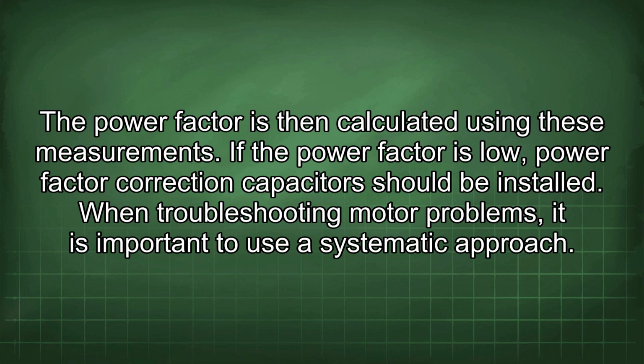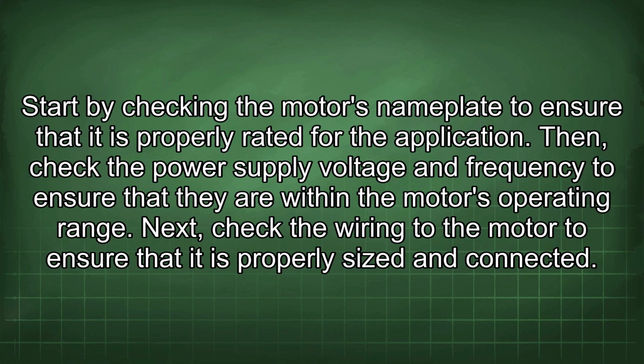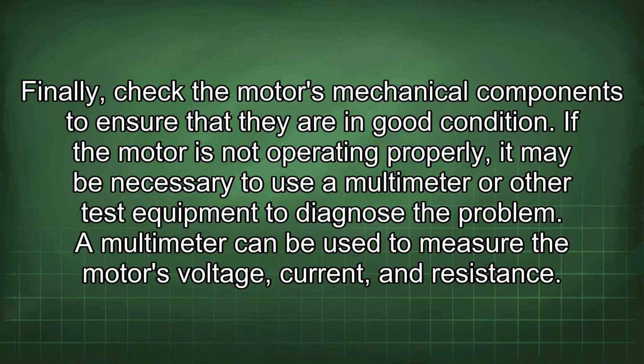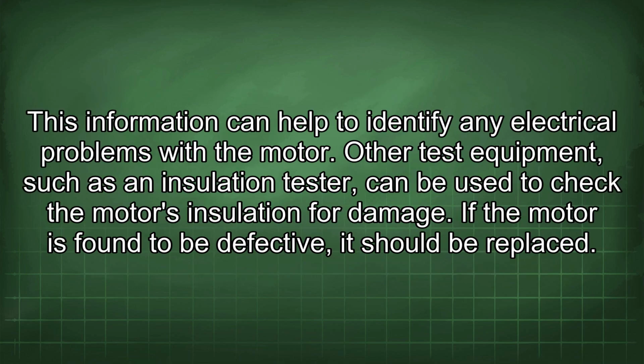When troubleshooting motor problems, it is important to use a systematic approach. Start by checking the motor's nameplate to ensure that it is properly rated for the application. Then check the power supply voltage and frequency to ensure that they are within the motor's operating range. Next, check the wiring to the motor to ensure that it is properly sized and connected. Finally, check the motor's mechanical components to ensure that they are in good condition. If the motor is not operating properly, it may be necessary to use a multimeter or other test equipment to diagnose the problem. A multimeter can be used to measure the motor's voltage, current, and resistance. This information can help to identify any electrical problems with the motor.